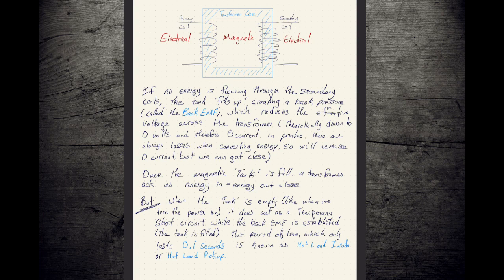So if we're in an outage condition and we turn the power back on, for a tiny fraction of a second, for the first cycle or so, that magnetic back pressure isn't present, and that coil looks an awful lot like a short circuit. And what we're going to see is a tremendously large flow of current during the first tenth of a second as that magnetic field gets set up. And so if you've got a circuit out, you flip the power on, for the first tenth of a second a huge flow of current is going to flow as you set up magnetic back pressure and fill those magnetic tanks in all the connected transformers. And so you get this temporary, very high overload current that only lasts a tenth of a second, and that's known as a hot load inrush or a hot load pickup condition.